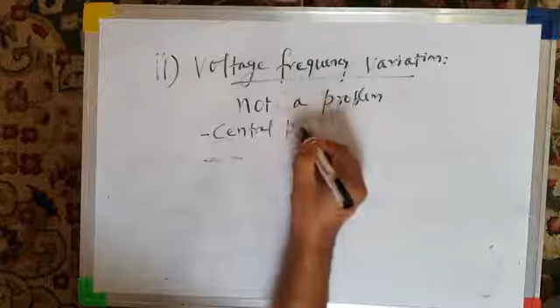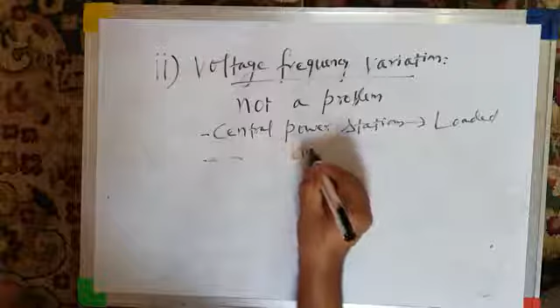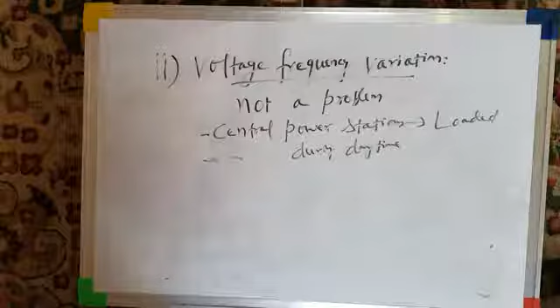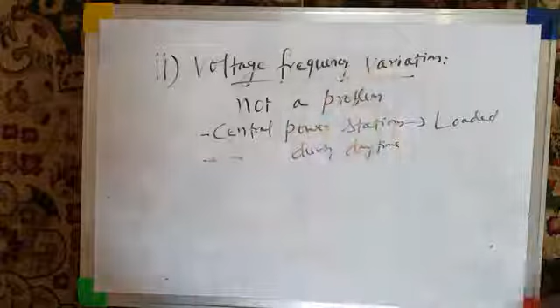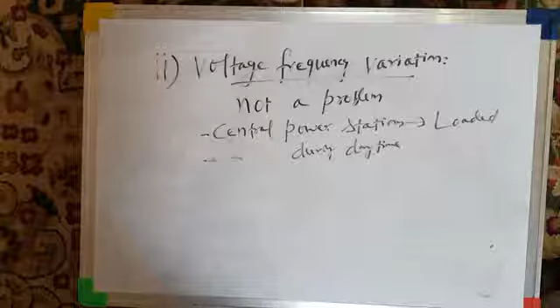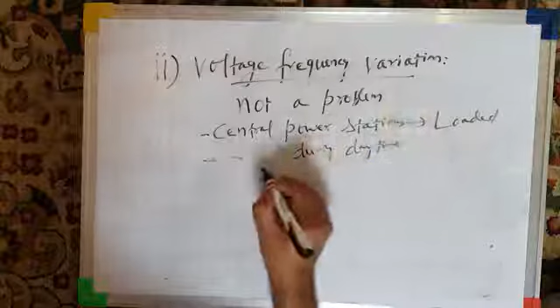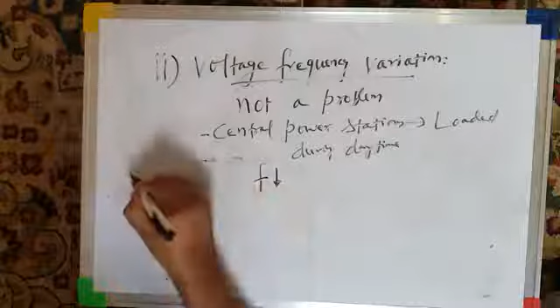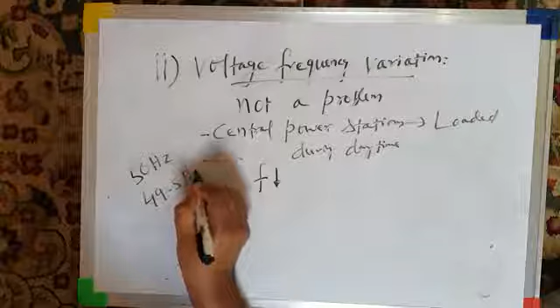For example, if you see central power stations or central generating stations, they are fully loaded during daytime. Because during daytime you have maximum load on the system: full industrial load, commercial load, because all shops, business establishments, offices, hotels, etc., are open during daytime, and then residential or domestic loads are also on. So that causes full loading of the system. And because of full loading, frequency lags a little bit. Like if your frequency was 50 hertz, it may drop from 50 hertz to 49.5 hertz. So there may be a drop of 0.5 hertz.